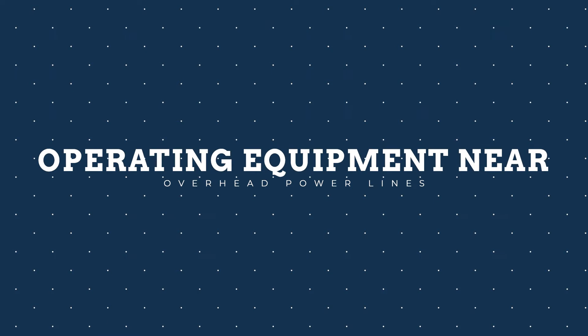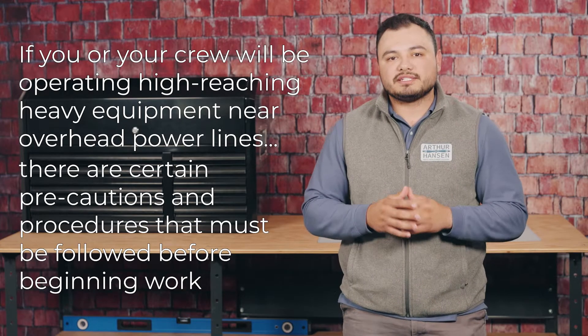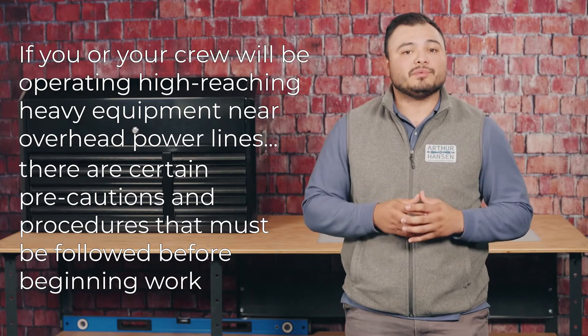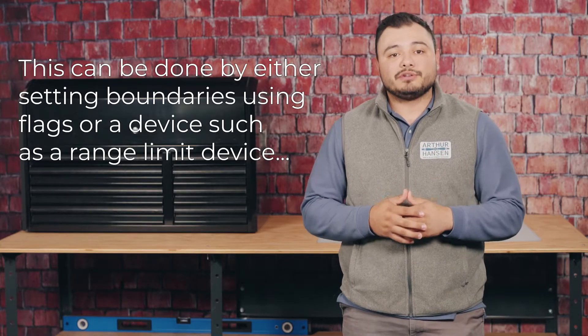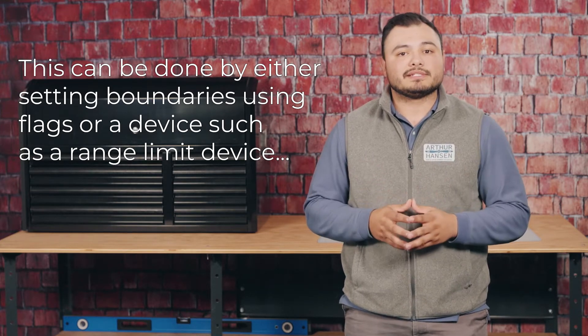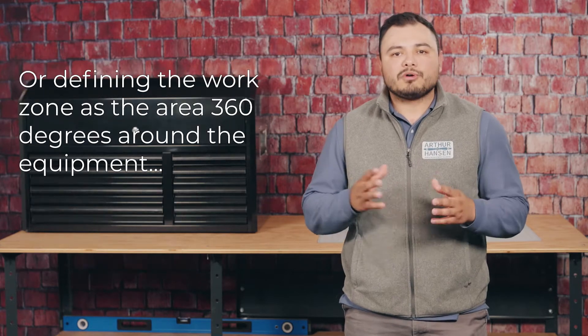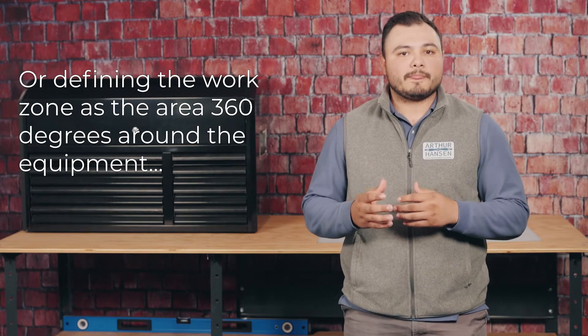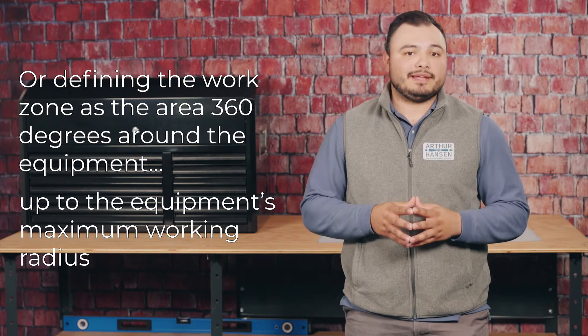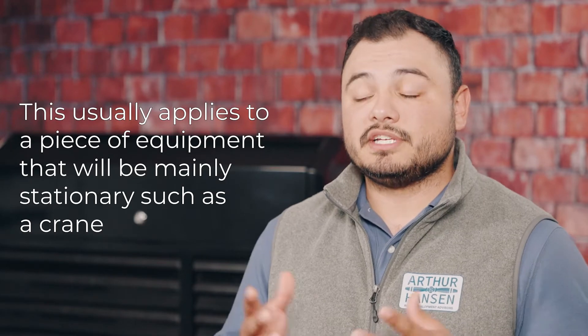If you or your crew will be operating high-reaching heavy equipment near overhead power lines, there are certain precautions and procedures that must be followed before beginning work. It all starts with identifying the work zone. This can be done by either setting boundaries such as flags or a range limit device, prohibiting the operator from going past those boundaries, or defining the work zone as the area 360 degrees around the equipment up to the equipment's maximum working radius. Keep in mind this usually applies to a piece of equipment that is mainly stationary, such as a crane.